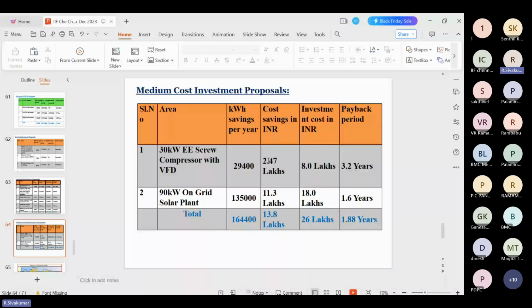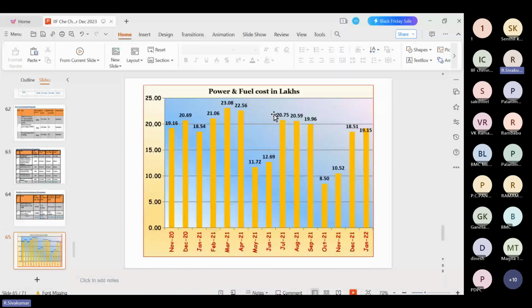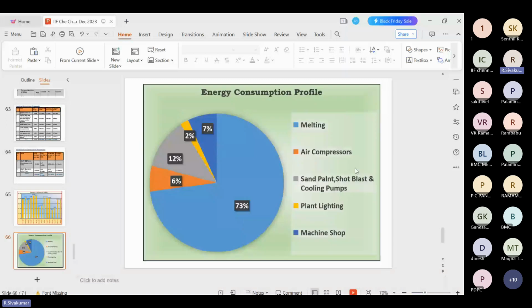This is the trend chart of the power and fuel cost in the foundry from December to January. Based on the production rate, the power and fuel cost also varied. This is the energy consumption profile. Melting is 73%. Normally the thumb rule says 70% for melting, but in this particular foundry 73% goes to melting, and the air compressor is 6%. Sand plant, shot blast, and the cooling pumps account for 12%, 2% for plant lighting, and 7% for the machine shop, because the machine shop is also established in the same unit.